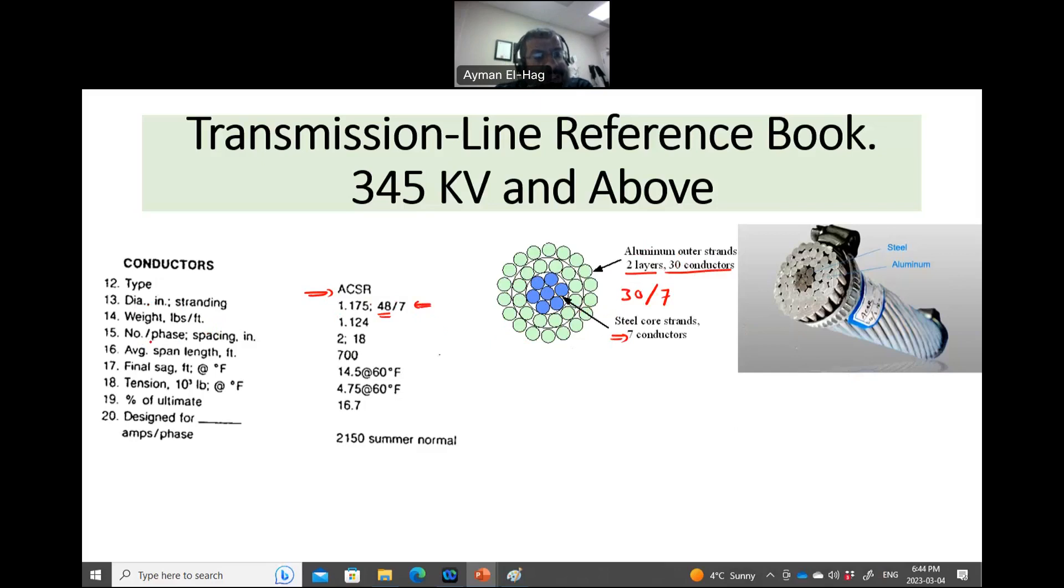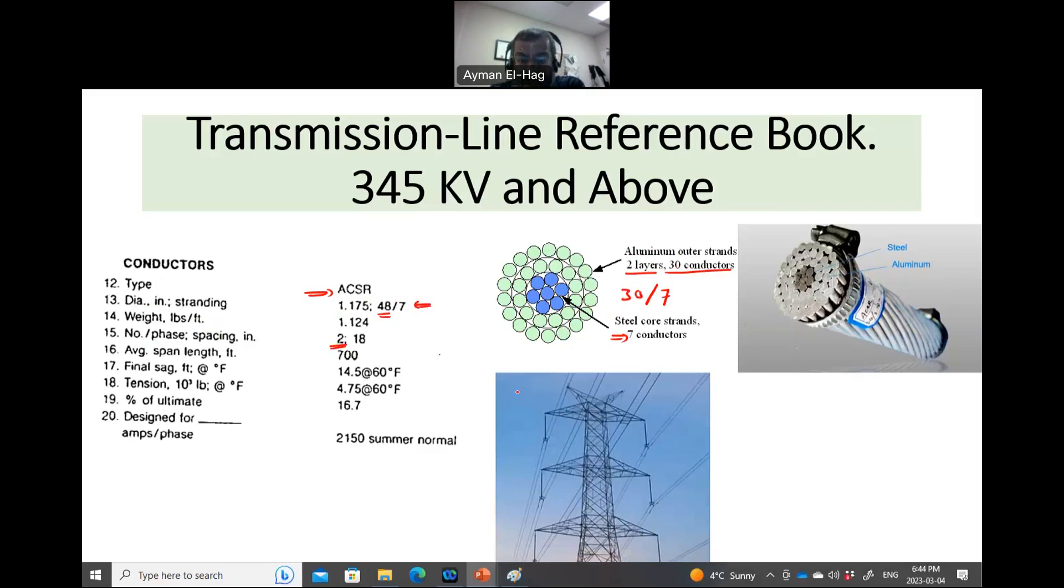Here it is number of phase, number of conductor per phase. It says here it's 2. And this is something very important. It means that this is a bundle of two. So if you look here, for example, to this tower we have here, you can see that per phase, there are two conductors. So this we call it bundle of two. So here each phase will have two conductors, spacing in inches, 18. This is the distance between these two conductors, between this conductor and this conductor. Basically, it is 18 inches. And this distance is very important in calculating the inductance and the capacitance of the line.